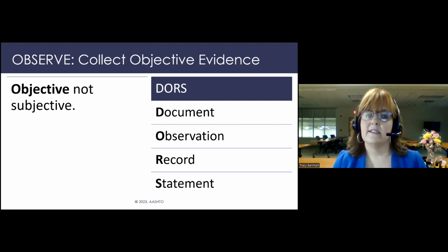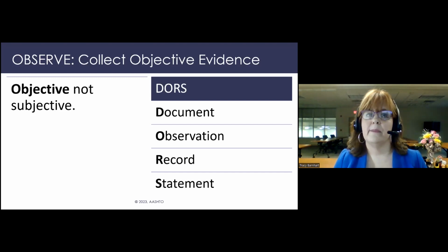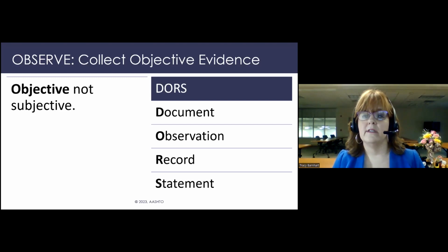And the S stands for statements. These are things that you hear during interviews, but you want to be careful with statements and make sure that you're understanding people correctly when they say things to you. So for example, you might ask somebody, explain to me how you were trained. That might be a good question. And then you're having an interview with somebody, they're telling you how they were trained, and you're looking at the QMS procedure for training, and these 2 things are not matching up at all. Well, that statement can and should be used as objective evidence to support nonconformity for that. So keep that in mind.